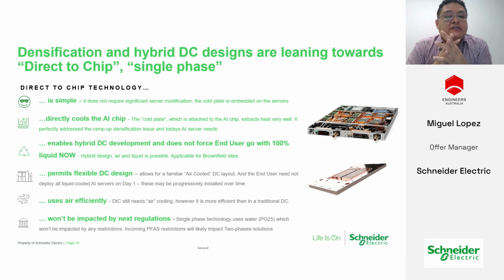Direct-to-chip technology permits a flexible data center design, which we're going to cover in a minute. It uses air efficiently - in other words, we are still requiring the use of air conditioning systems such as CRACs, CRAHs, fan walls, and in-row coolers. And it won't be impacted by the next regulation, so I'll be covering the so-called next industry guidance by the likes of ASHRAE.